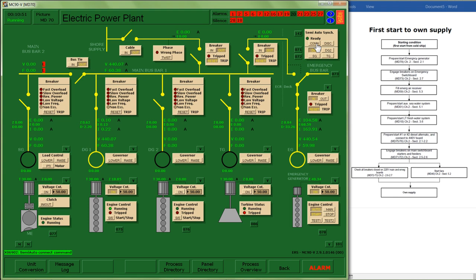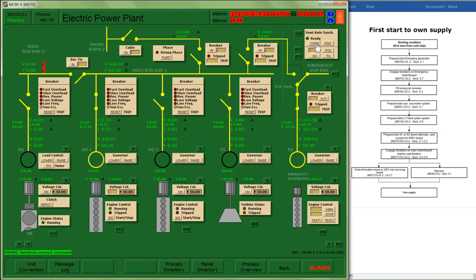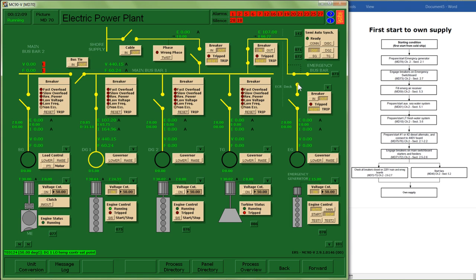I can note that my cooling water supply seems to be being reduced. If I go back to my seawater system number one, you can note that my seawater pump turned off, also indicated by a low pressure alarm. The reasoning for that is that when I connected my emergency bus, that was not a smooth transition. It was a sudden switch from system to system, which meant I may have had a momentary loss of power. Momentary losses of power means some equipment might turn themselves off, and I'll need to make sure I restart them.